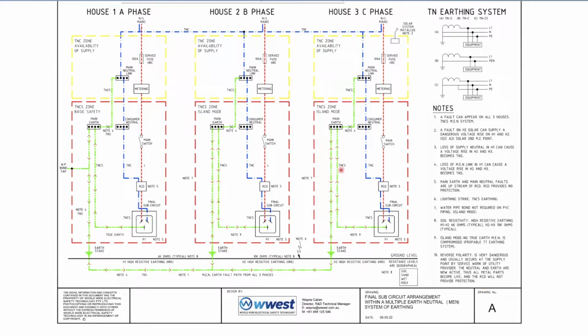If you look right up the top, we've got house 1, and it's on A phase. Then when we come across, we've got house 2, that's on B phase. And then house 3 is on C phase. So it's typically balanced across a three-phase TNCS earthing system.